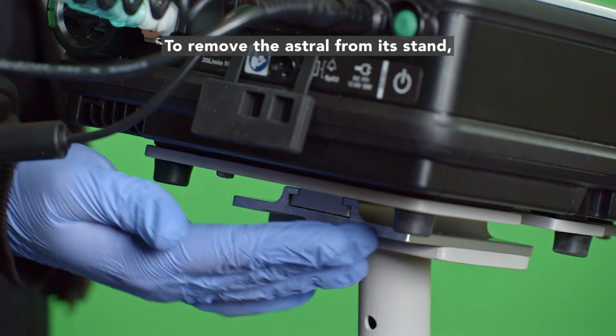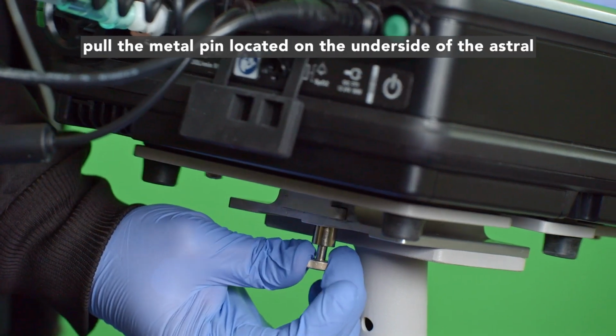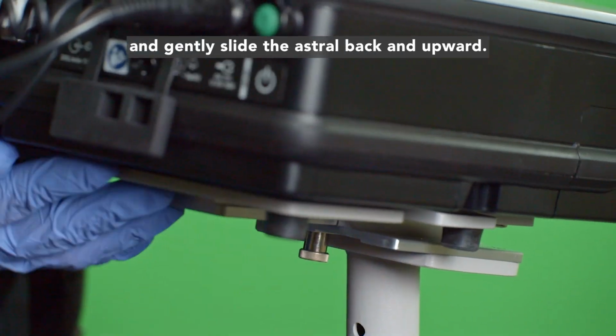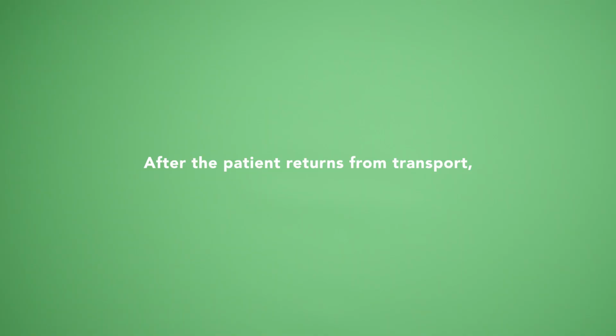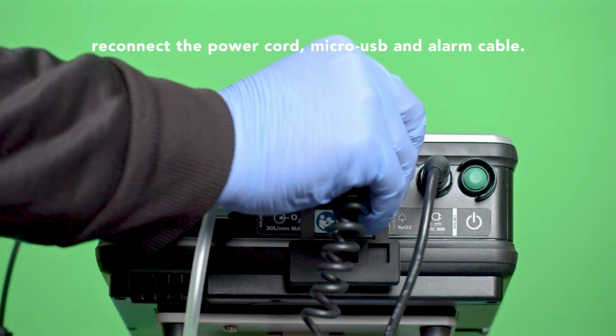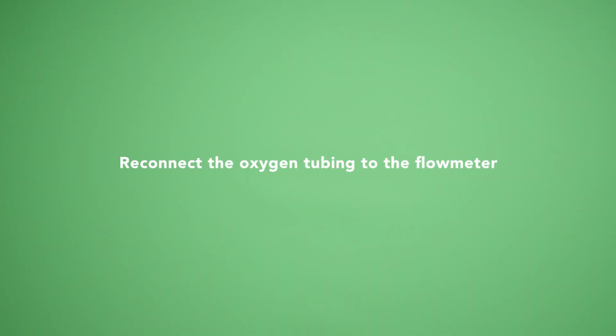To remove the Astral from its stand, pull the metal pin located on the underside of the Astral and gently slide the Astral back and upward. After the patient returns from transport, reconnect the power cord, micro USB, and alarm cable. Reconnect the oxygen tubing to the flow meter at the wall and adjust to the appropriate liter flow.